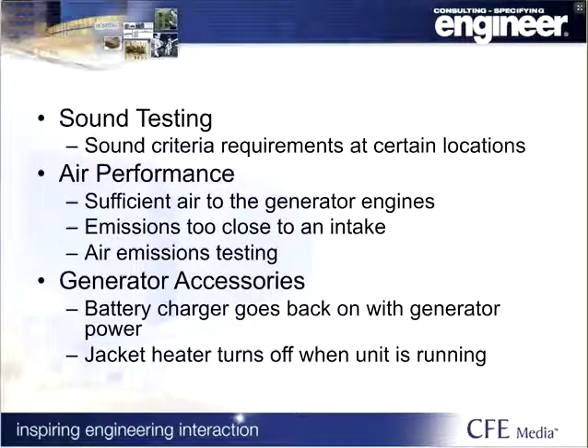Sound testing might be needed if you're in a certain area that has a requirement for a certain sound level at the property line. A lot of times the generators aren't front and center on the property. They try to put them on the back, and we need to be mindful of that. Air performance is certainly an important feature. Emissions: I've seen generator systems where the exhaust is too close to an intake, and it's actually pulling the exhaust fumes back into the building because the air that the radiators need is so much. And then, of course, I mentioned a couple of the accessories earlier.